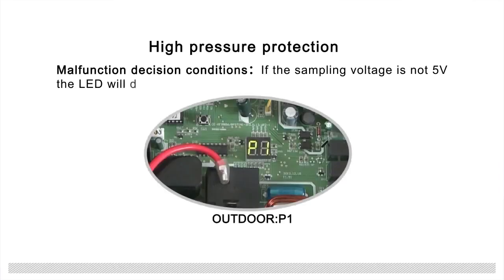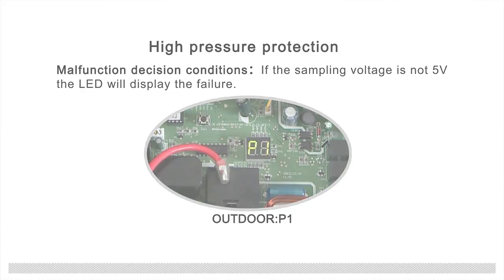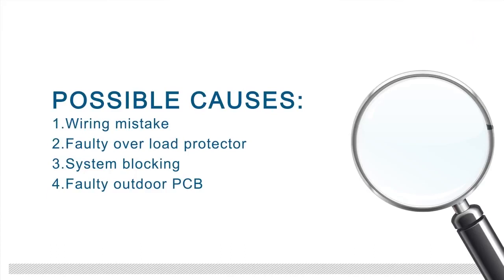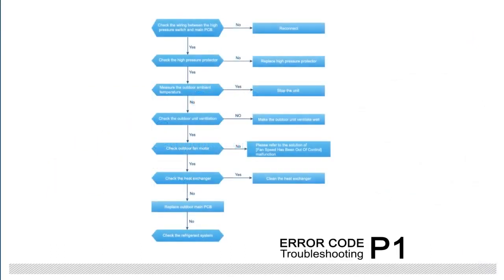High pressure protection malfunction conditions: if the sampling voltage is not 5 volts, the LED will display the failure. The failure may be caused by wiring mistake, faulty overload protector, system leakage or blocking, or a faulty outdoor PCB. Troubleshooting is shown in the figure.